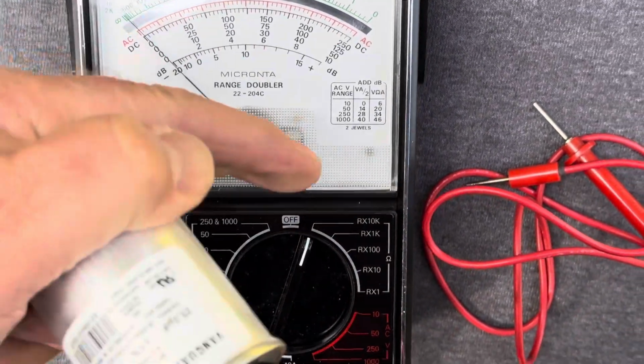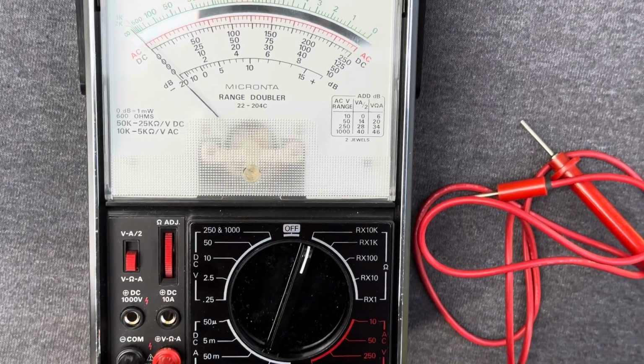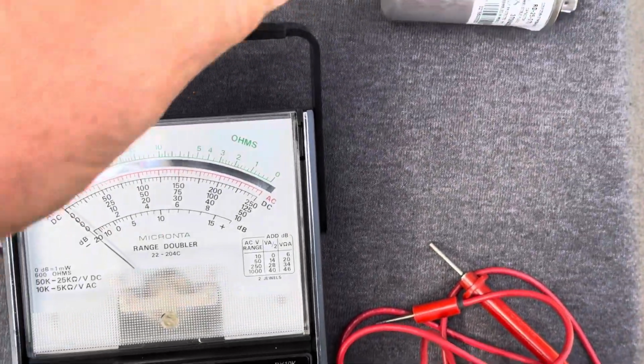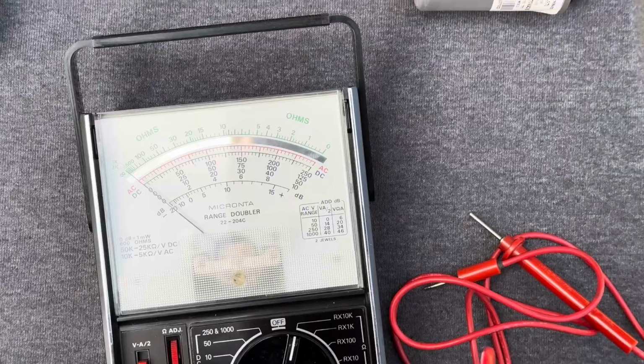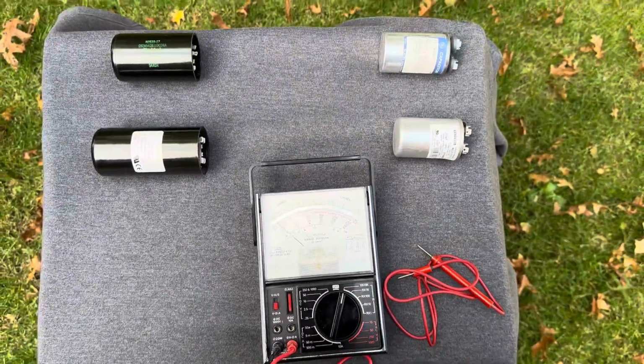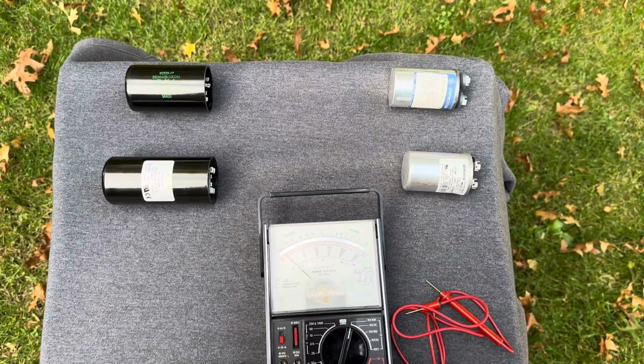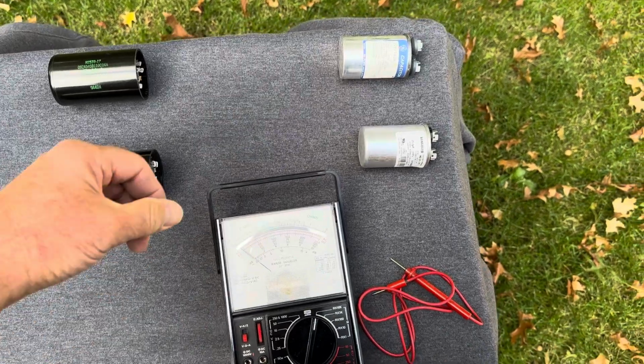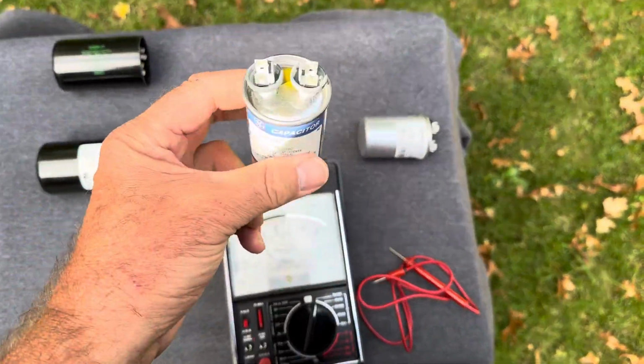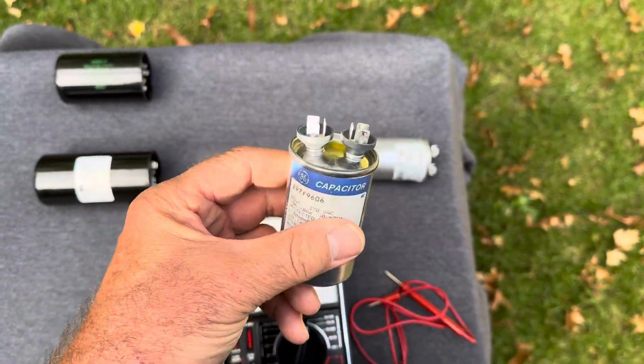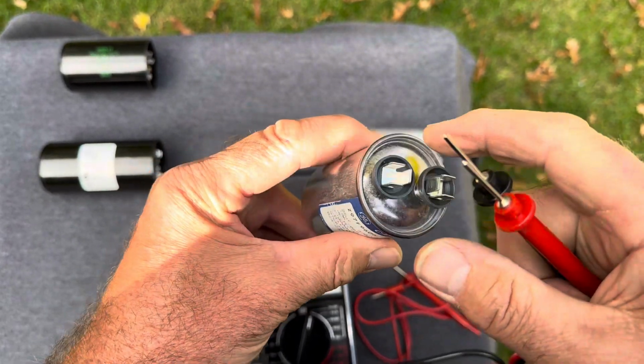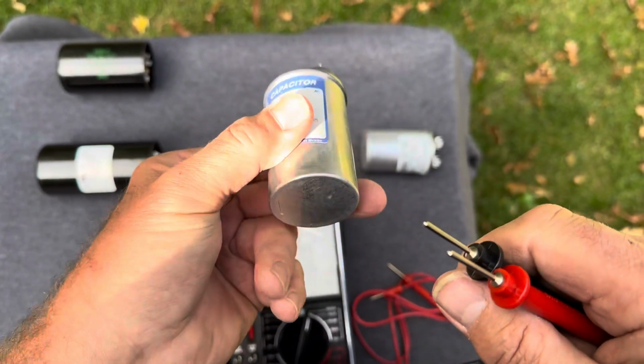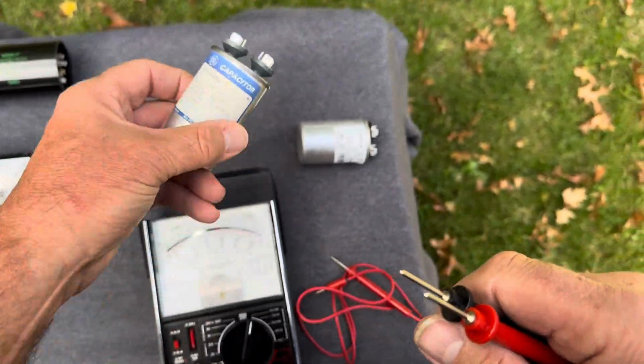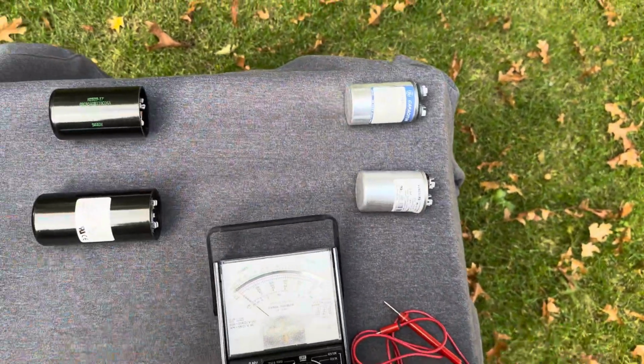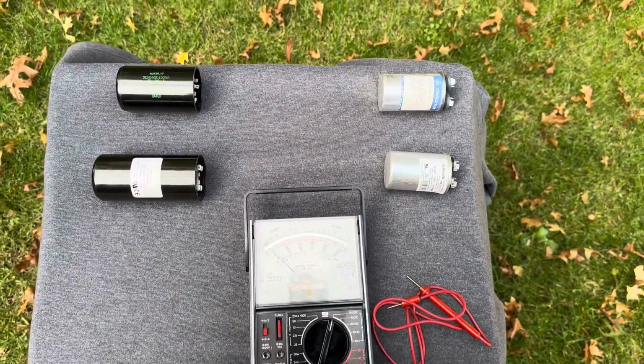You should see that deflection, and then the needle should start to fall back. That's just one quick way you can test capacitors on your own to see if you have a problem. And like I mentioned, just physically look at the capacitor - this run capacitor is bulged, obviously defective. So that probably explains why the compressor wasn't running properly.